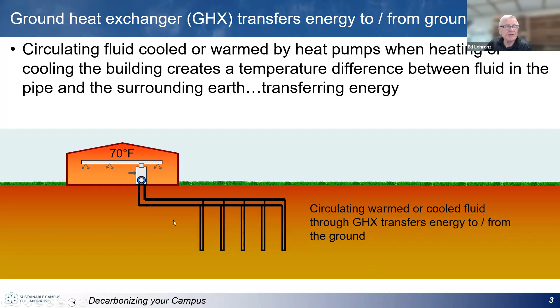The gray areas are the outdoor air temperatures in Winnipeg in a typical year. The green is showing what the ground temperature is doing when we're taking heat from it or dumping heat into it. So it gets as high as about 80 or 85 degrees Fahrenheit, or about 25, 30 degrees C, and gets down to around freezing or just slightly below freezing, depending on what we're doing and the time of year. This is about the coldest time of year that you're going to see in the ground.